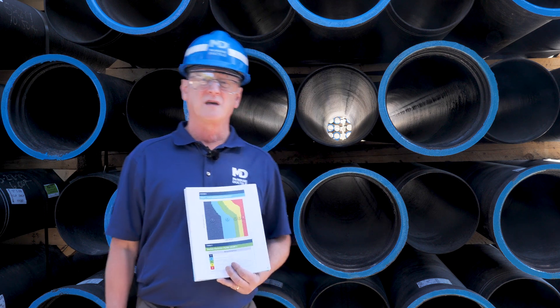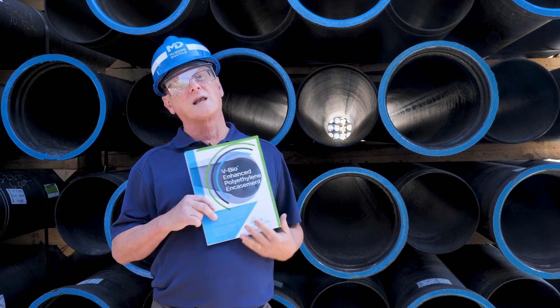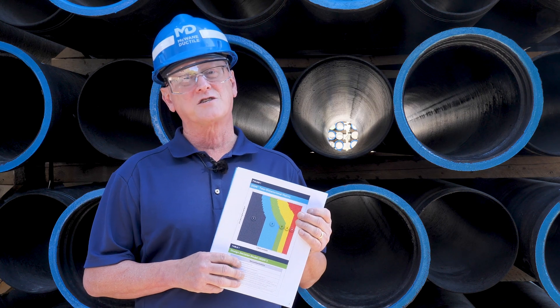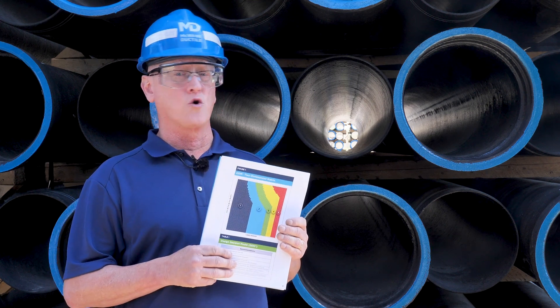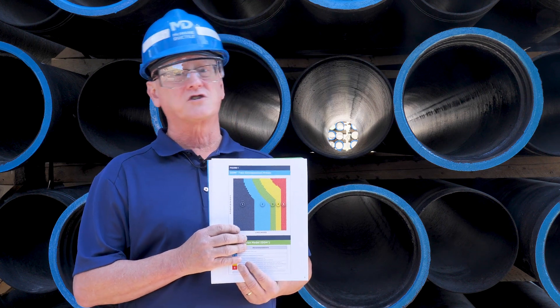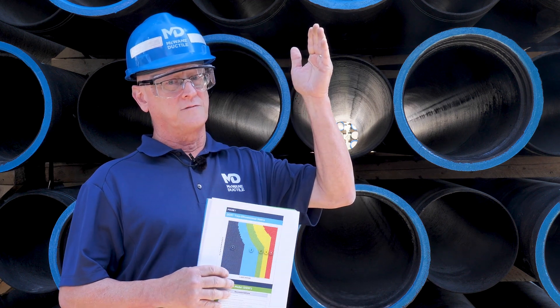Second, and more importantly, if your project falls in either zones 4 or 5 of the Design Decision Model, it is recommended that you specify V-Bio enhanced polyethylene encasement along with the metalized zinc coating, or V-Bio along with cathodic protection in some extreme circumstances. The Design Decision Model, or DDM, was established through a joint effort between the Ductile Iron Pipe Research Association and CORPRO. The DDM plots recommendations for corrosion and the consequences of failure, ranging from the standard shop coat or bituminous seal coat in category 1 to the category 5 recommendations. To learn more about the DDM, click here to watch a video from one of my colleagues.